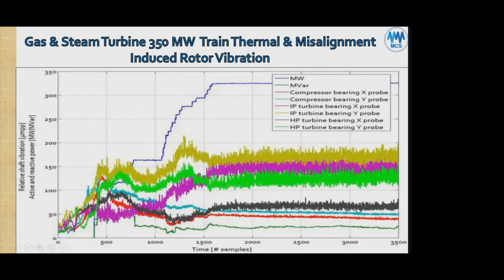And once it's reached rated speed, you can see the rated speed basically right here. So from here on, we're seeing variations in the vibration at each bearing. The red color is the compressor bearing X probe, so it'd be the gas turbine compressor bearing. And the blue would be compressor bearing Y probe. Then we have the IP turbine bearing X probe, purple, over here. And we have the IP turbine bearing Y probe, which is the highest value here. Then we have HP turbine.